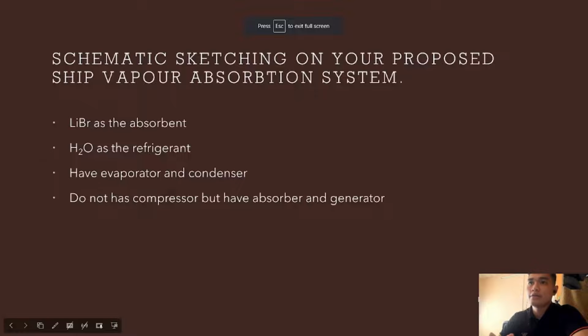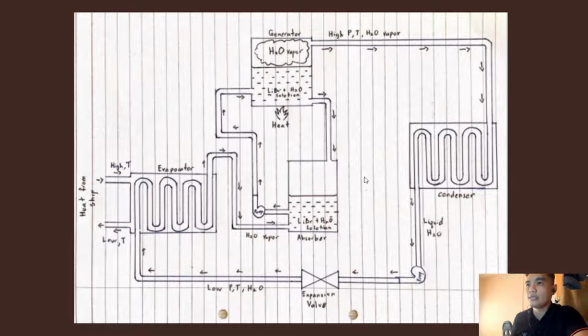Alright, now we will discuss the schematic diagram of the ship vapor absorption system. The system will use lithium bromide, LiBr, as the absorbent, and H2O, which is water, as the refrigerant. And this system has the same evaporator and condenser as the normal refrigeration cycle. It will not have any compressor, but has an absorber and generator. This is the schematic diagram for the vapor absorption system.